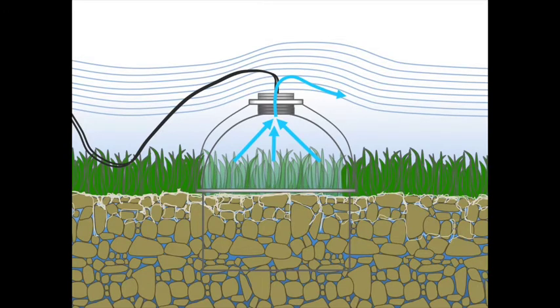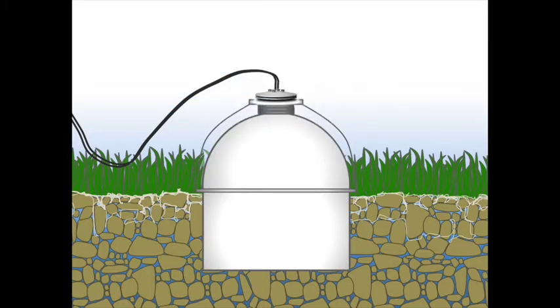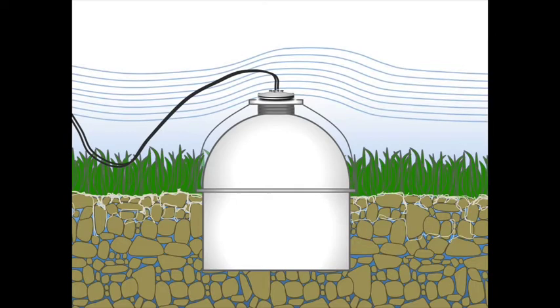In order to minimize this effect, our instrument has a patented pressure vent that helps maintain a constant pressure inside the chamber that matches the atmosphere outside.